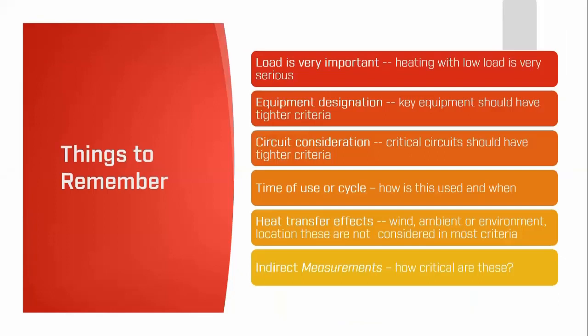There are many considerations when looking at thermal images of electrical installations. We need correct loading readings — heating at low load is a serious concern. Equipment designation speaks to the importance of the component in the process. Circuit consideration accounts for the position of the component. Time of use determines the amount of heating — 50% duty cycle images very differently than 100% continuous. And understanding the environment and cooling effects will affect our evaluation in many ways.